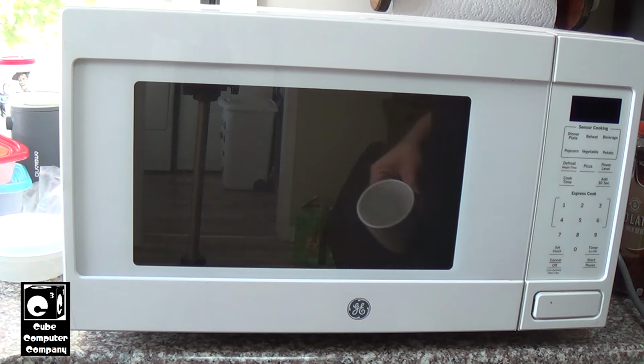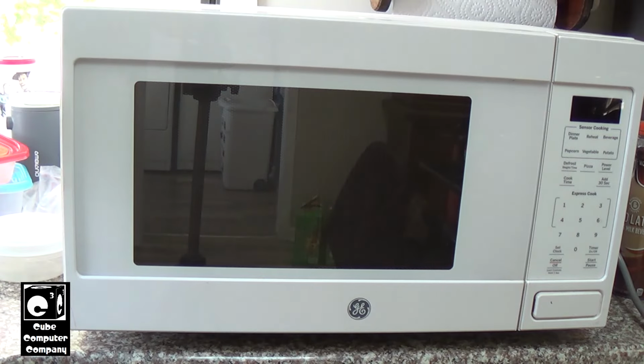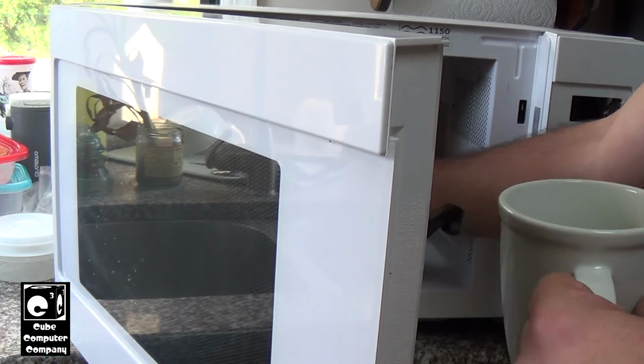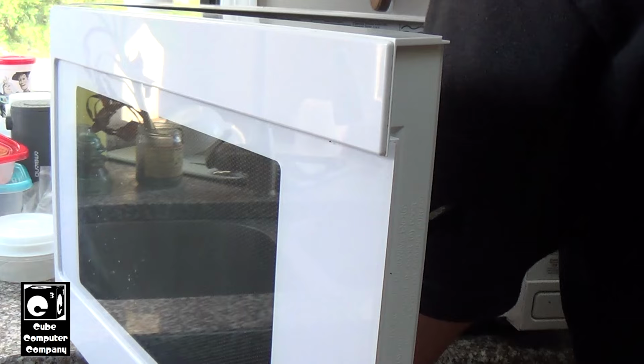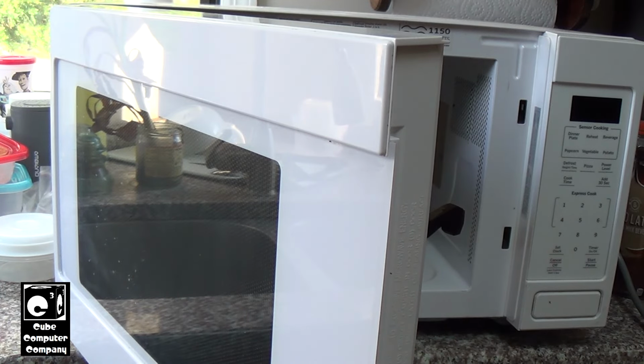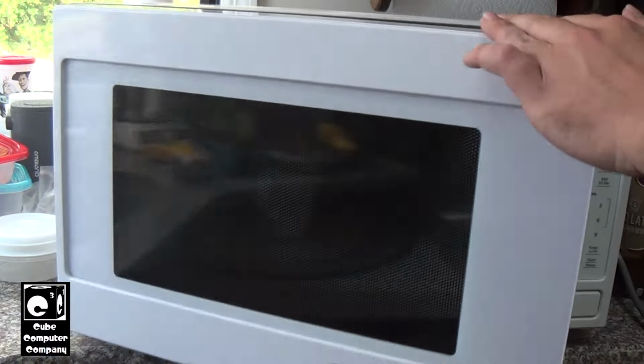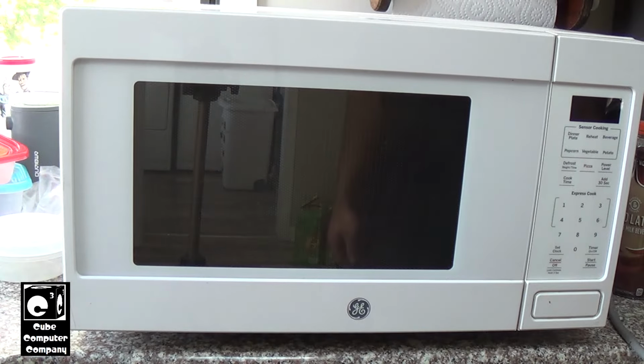Okay, so now we're in the kitchen where we have 20 amp receptacles strong enough to handle a countertop microwave. What I'm going to do is put this mug in there with some water. That way there's a load. Normally I wouldn't do this right away, but there is a chance that this thing could fire up immediately once it's plugged in. I want to make sure that there's load. Again, it should not fire up right away. That's what it's supposed to do. It's not supposed to start on its own. We should get a beep, and we should get something like a PF on the display there.